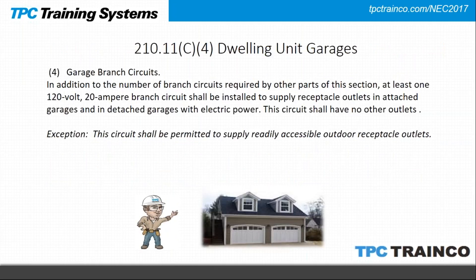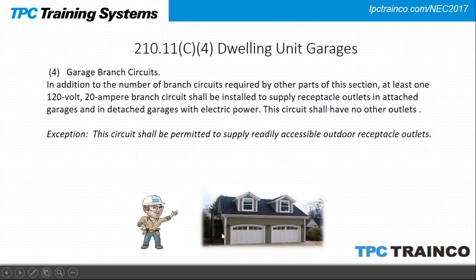Section 210.11 C4 addresses dwelling unit garages. Historically, a garage circuit was dedicated only to receptacles in the garage with no other outlets. Now there is an exception: this circuit is permitted to also supply readily accessible outdoor receptacle outlets. For a detached garage, this is very handy — you wouldn't have to run two separate circuits. One circuit can supply both the interior garage receptacles and the exterior outdoor receptacles on the same circuit.